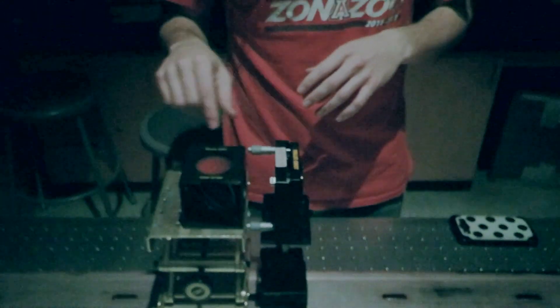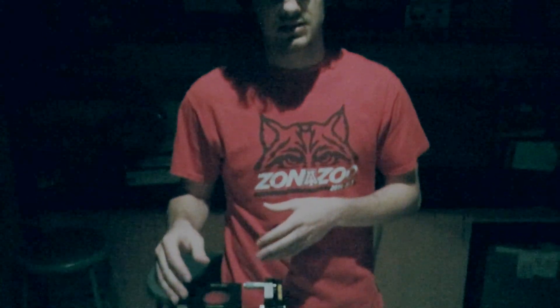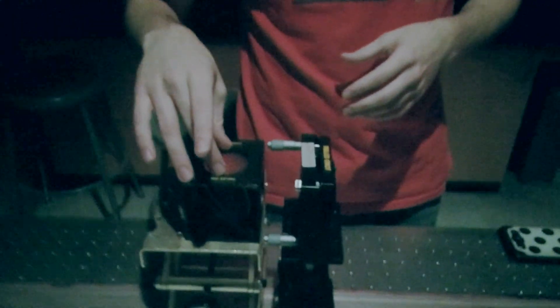For this one we're using the low power lens, and what we're going to do is use the fringe spacing and the angle to determine the focal length of the lens. To do that we're going to take images of this, and we know the diameter of this circle, and we will use image processing software to calculate using pixels the spacing and the angle.